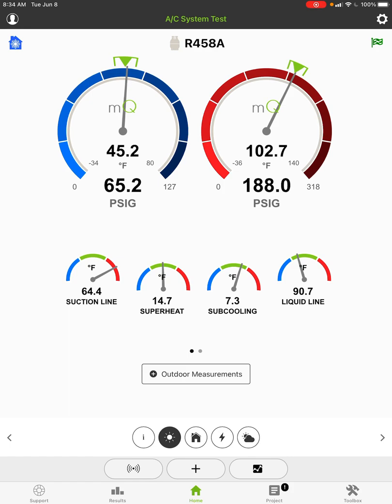Then on the high side you look at 90.7 and 102, it looks like a subcooling of approximately 12 degrees. Yet the superheat and the subcooling shown are 14.4 and 7.1.